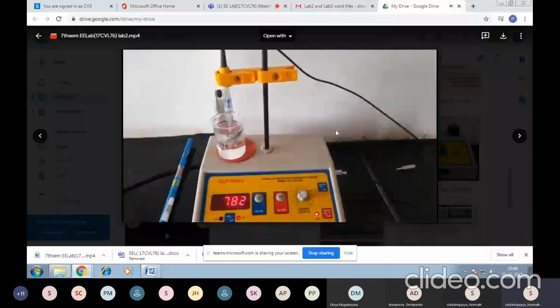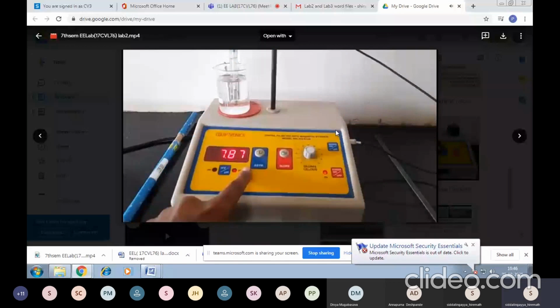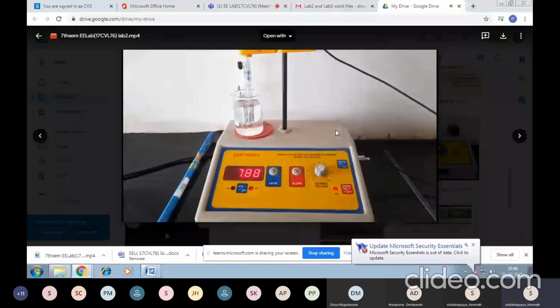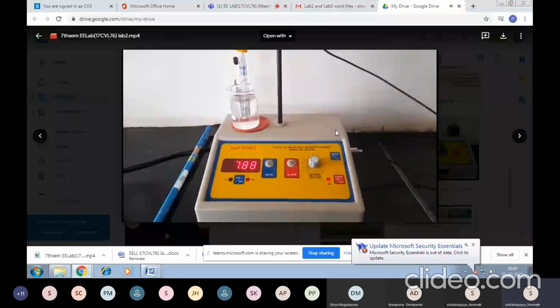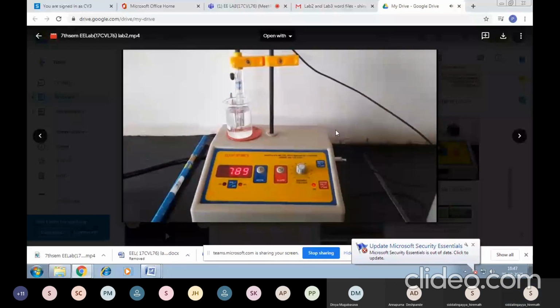Asymmetry potential. This is to nullify asymmetry potential of the electrode. In general, asymmetric potential remains fairly constant for a period of few weeks for a given pair of electrodes. Thus, once set, it may need adjustment once in 3 months.